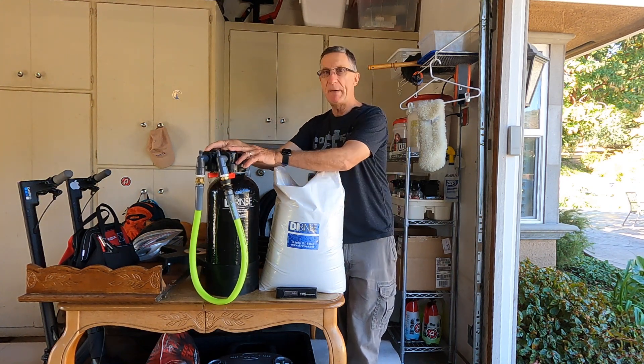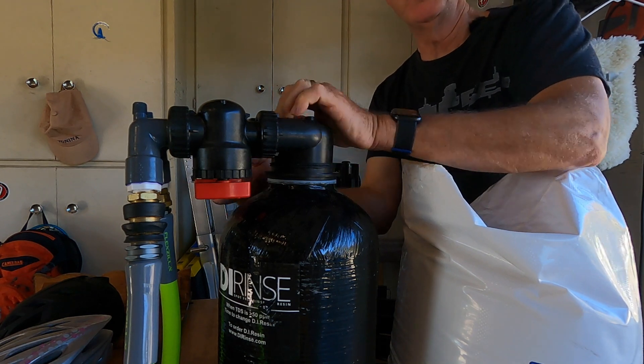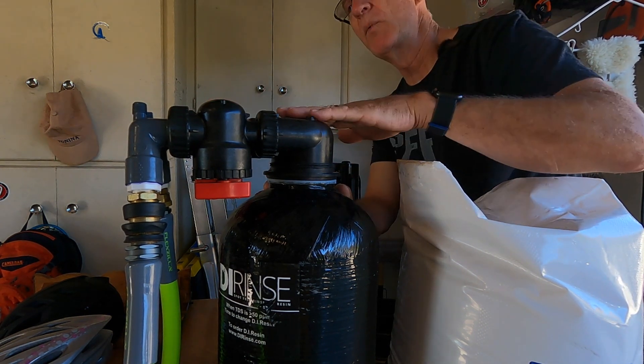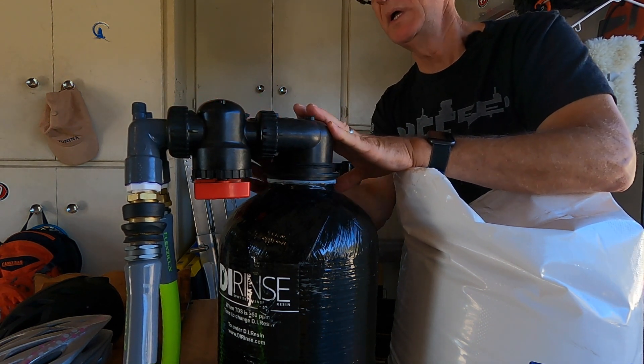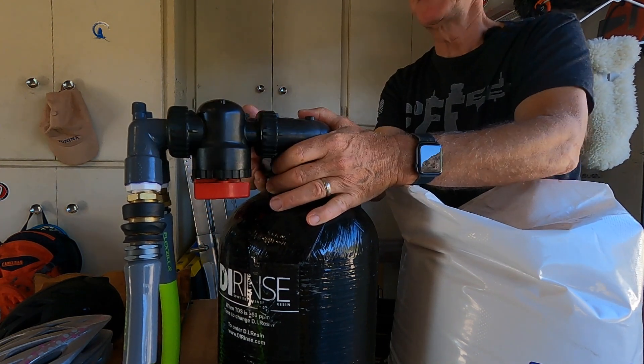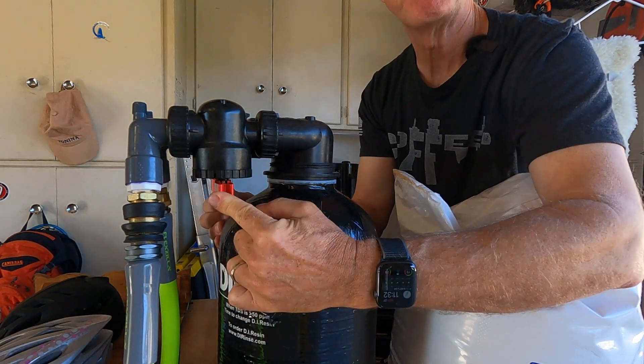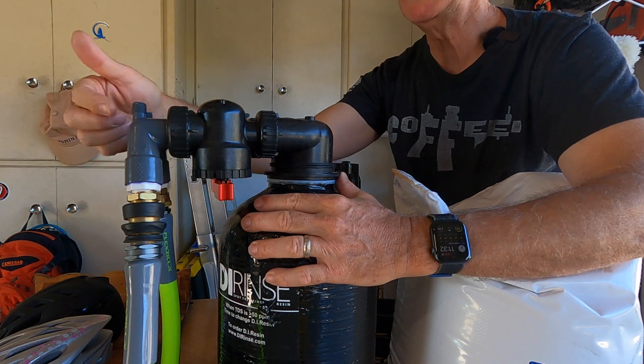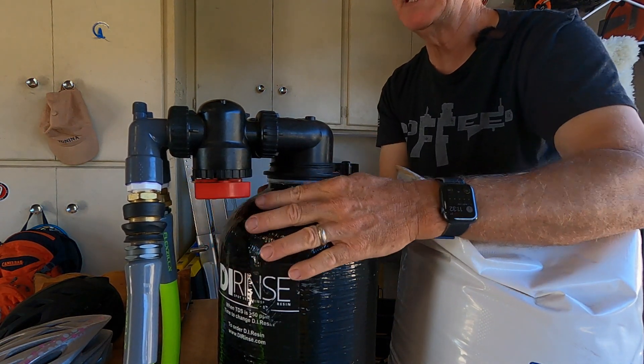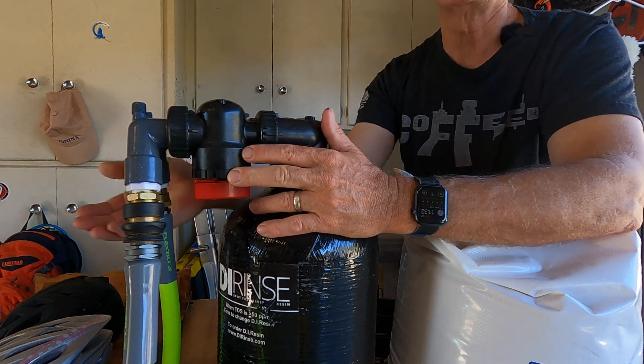This is the bypass system. You'll notice these valves are upside down — when the tank comes to you, these valves will be on the top, which is a problem for clearance in our coach bays. The valves get precariously close to the bay door. So I reversed the screwed-on couplings and put them upside down. In this position the valves are in bypass, closing the water channel off so it circulates from input to output without going through the tank. Or you leave them in the flow-through position and water comes in, chases through the DI resin, and comes out the output. I just leave it in the open position all the time — it also helps it drain easier when I disconnect it.